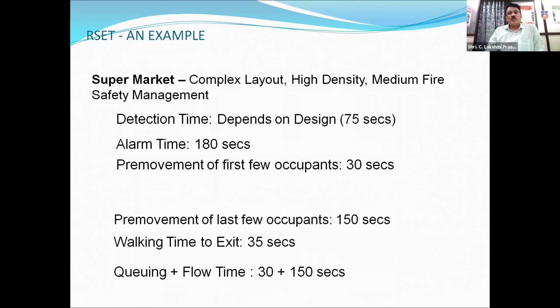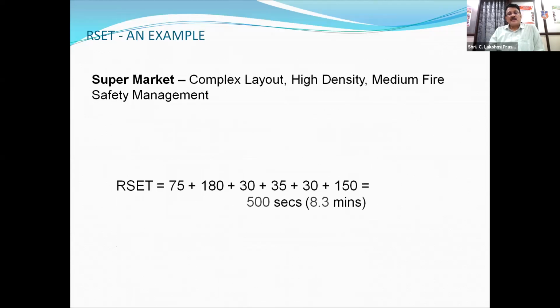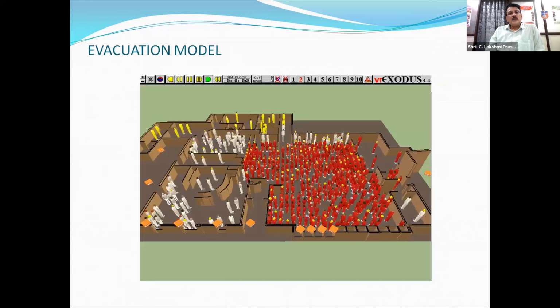You can see various times in a supermarket, for example. Detection time depends on design. If you take the minimum as 1.25 minutes, 75 seconds, alarm time 180 seconds, pre-movement of first few occupants 30 seconds, pre-movement of last few occupants 150 seconds, walking time to exit 35 seconds, queuing plus flow time 30 plus 150 seconds. So totally it is coming to 500 seconds, 8.3 minutes. This is the required safe exit time, the egress time. Evacuation modeling is how they show the movement of the people by fixing various parameters.